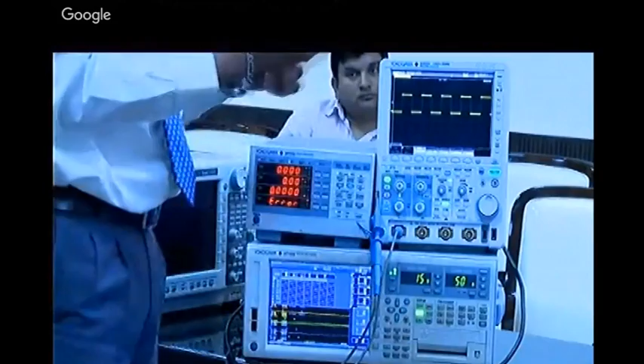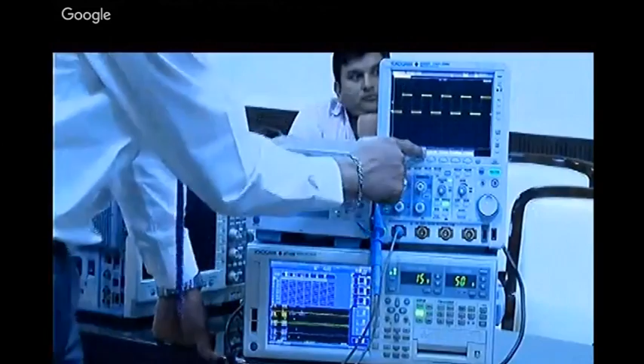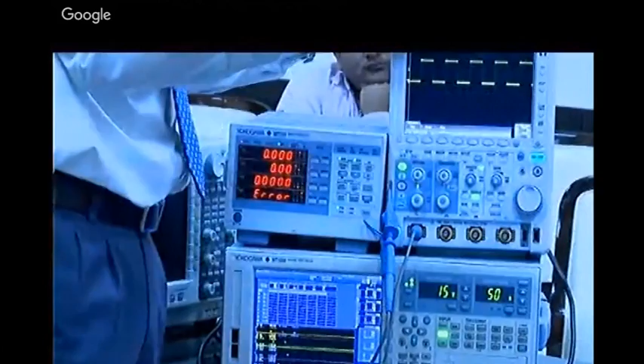If you select pulse width, you can select which channel and then define the pulse width, say 4 seconds - more than 4 seconds, less than 4 seconds, between 4 and 5 seconds, or out of 4 to 5 seconds. That you can define here, and see whether you're able to view it or not. You can connect it to a projector also. Out of range, you can select below 4 seconds and above 5 seconds - that also you can configure. So these are all configurable options which you can do.